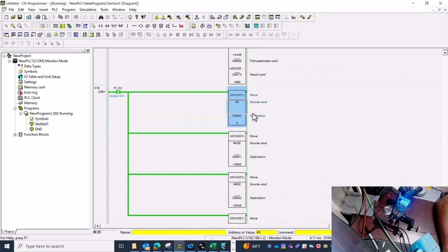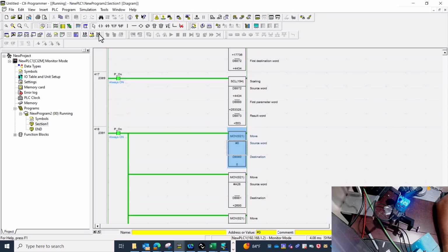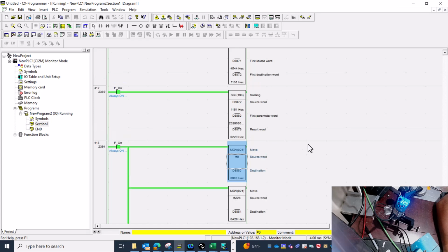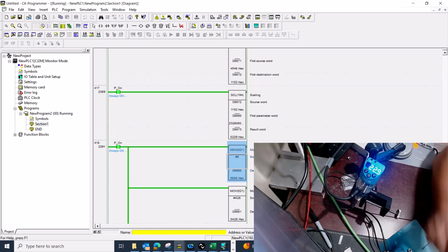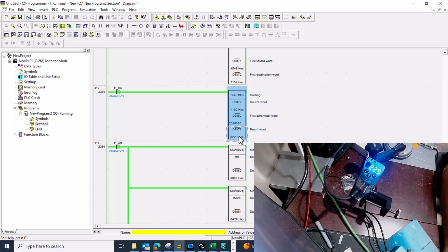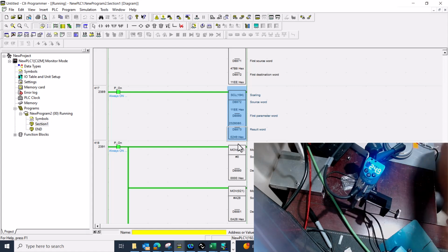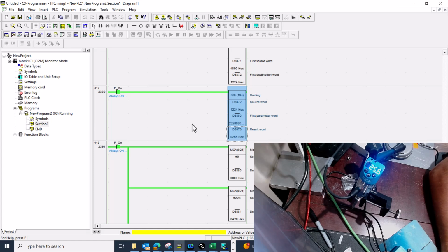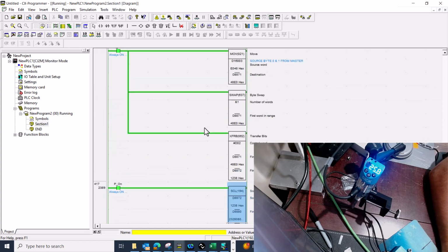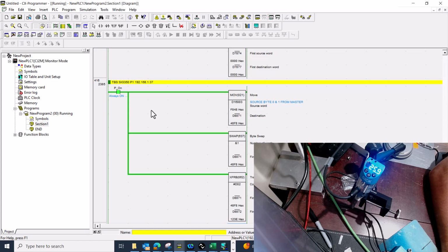And now you can see if I come here and go back to hexadecimal, I've got the sensor here, and we can look at the scaled value here. If I start to warm the sensor up, we should see that those 2 values are the same. Anyway, that's how you take the TBS from SICK, bring it over IO-Link, and scale the data to get an actual temperature value.